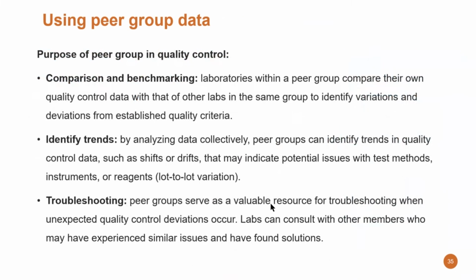Laboratories within a peer group compare their own quality control data with that of other labs using the same instrumentation, and see if they can identify variations and deviations from the established quality control criteria. Identify trends by analyzing data collectively. Peer groups can identify trends in quality control data, such as shifts and drifts, that may indicate potential issues with your test methods, instruments, or reagents, especially if there is a lot change. And you can use it for troubleshooting. Peer groups also serve as a valuable resource for troubleshooting when unexpected quality control deviations occur. So labs can consult with other members who may have experienced similar issues, and maybe they have found solutions helping you on your way to fix that issue.